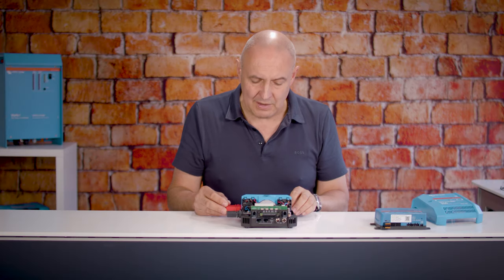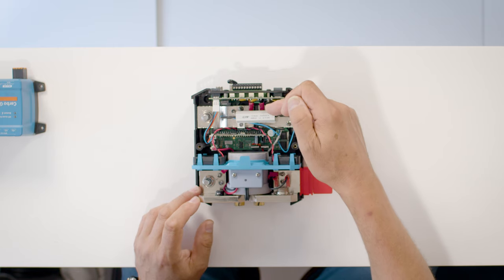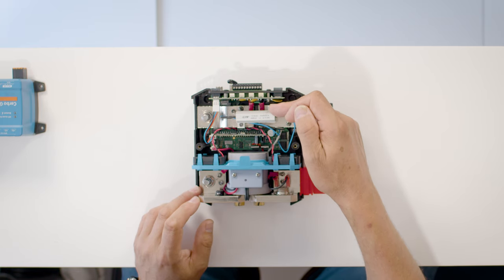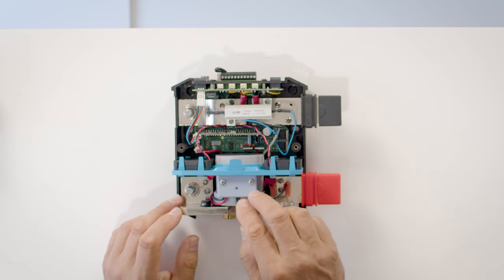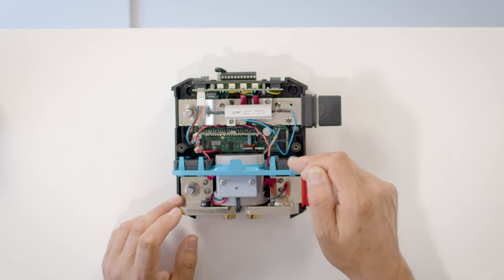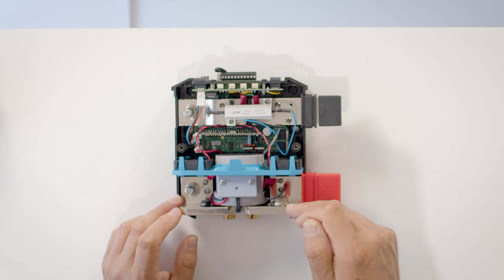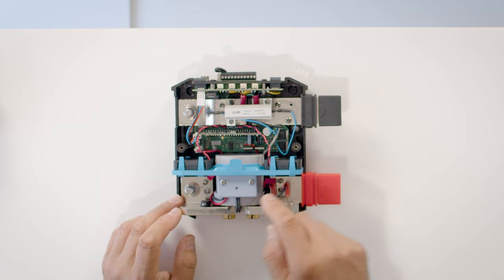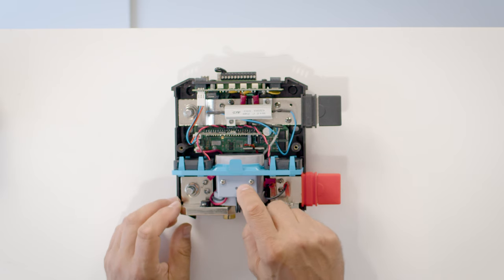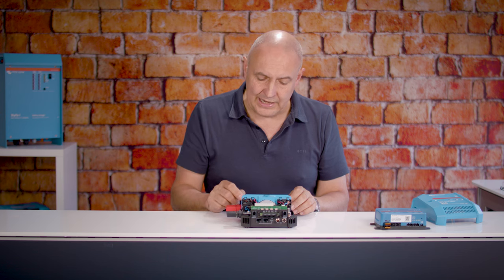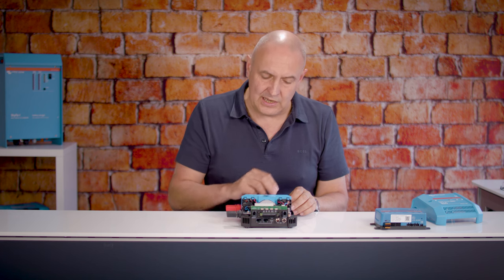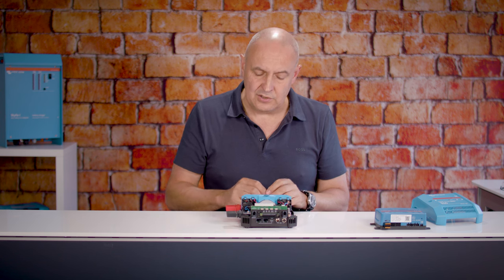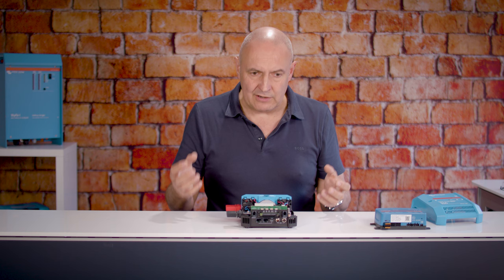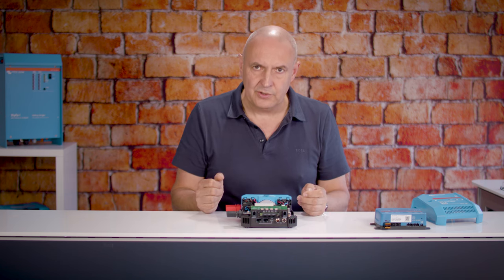So built into this BMS is what's called a pre-charge circuit, and this resistor here is the device that performs that kind of pre-charge function. So when we go to turn on the contactor, the microcontroller within the BMS will actually connect the input and the output side of the busbar through this resistor for a period prior to closing the main contactor contacts. And what that allows us to do is to bleed a controlled amount of power from the batteries into the Quattro or Multi Plus to pre-charge all of those capacitors, so that they're all full before we actually turn on the main contact, and therefore avoid or mitigate the risk of that contact erosion.